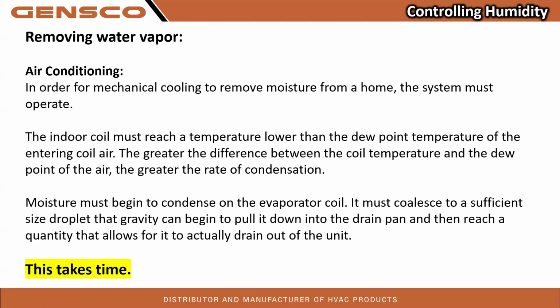So we need the coil to have a temperature lower than the dew point. Moisture must begin to condense on the coil. It must coalesce to a sufficient size droplet that gravity comes into play. And then it must have enough quantity that it can actually be pulled down into the drain pan and that it will actually drain out of the unit. And the big key to this one, and why we have humidity problems in cooling in some cases here in the Northwest, is that this takes time and we don't have a load.